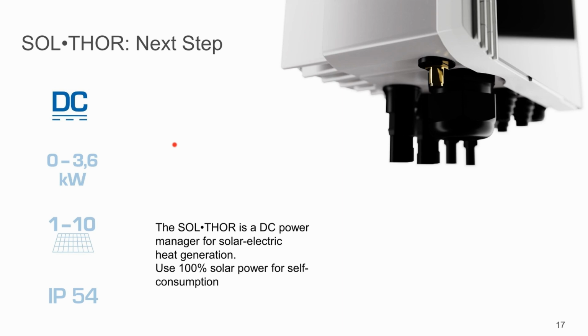All right. And reason number 3 is also a safety reason. It's not possible to deactivate an immersion heater with a thermostat like this when there is direct current on the switch. Imagine what happens when you have direct current on an AC switch: when the switch opens, you have an arc in between, and this arc will destroy the switch. In the worst case, it can cause a fire.